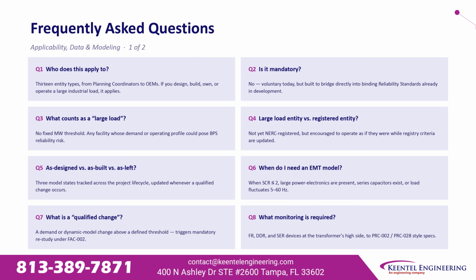What's the difference between as designed, as built, and as left? 3 model states tracked and updated whenever a qualified change occurs. When do I need an electromagnetic transient model? When short circuit ratio is 2 or below, large power electronics are present or load fluctuates rapidly. What is a qualified change? A demand or model change above a set threshold that triggers mandatory restudy. What monitoring is required? Fault, disturbance, and sequence of events recording at the transformer's high side.